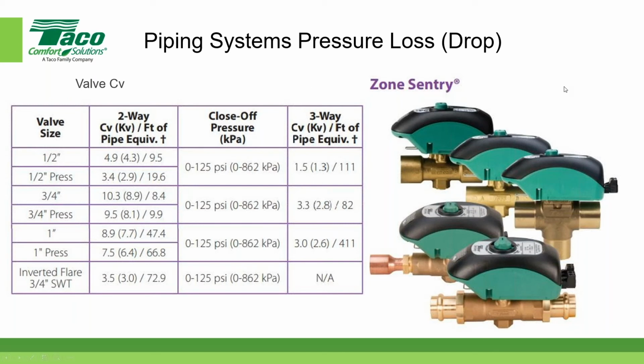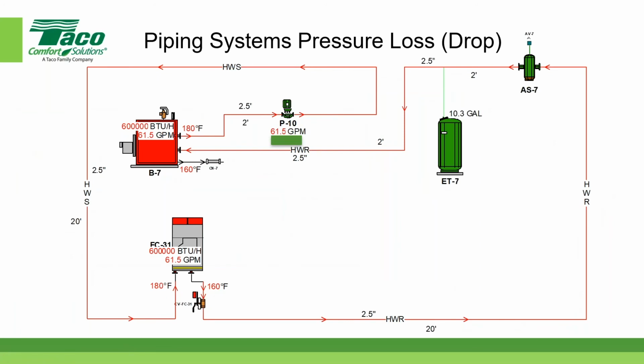Okay, continuing on. For the first time, we're starting to get into the meat of things. Here we have a very, very simple piping diagram. In this particular case, the piping diagram has a boiler, a circulating pump, and pipe with a bunch of fittings and elbows in there. It also has a control valve, an air and dirt separator, and an expansion tank. So we want to figure out what the pressure drop would be for this entire piping system, including the pipe, the fittings, and the equipment.